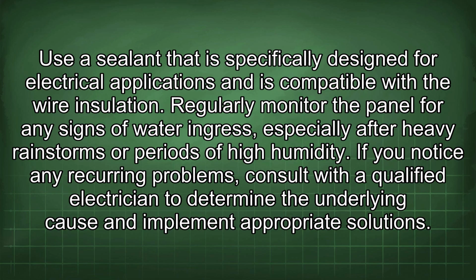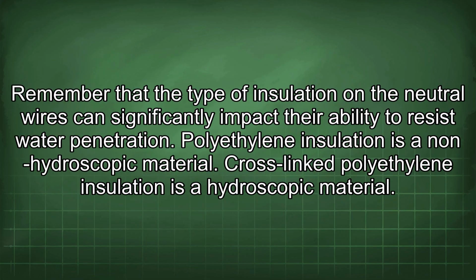Regularly monitor the panel for any signs of water ingress, especially after heavy rainstorms or periods of high humidity. If you notice any recurring problems, consult with a qualified electrician to determine the underlying cause and implement appropriate solutions. Remember that the type of insulation on the neutral wires can significantly impact their ability to resist water penetration. Polyethylene insulation is a non-hygroscopic material. Cross-linked polyethylene insulation is a hygroscopic material.